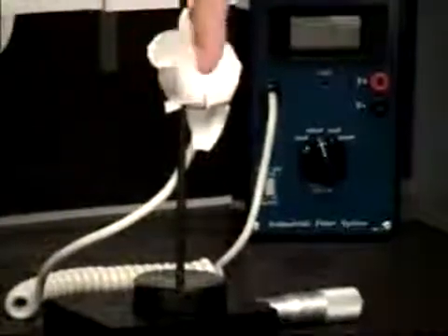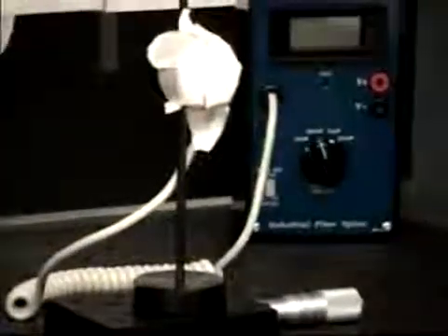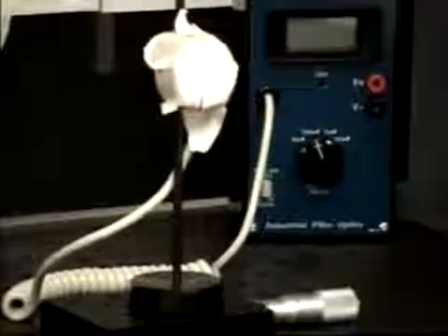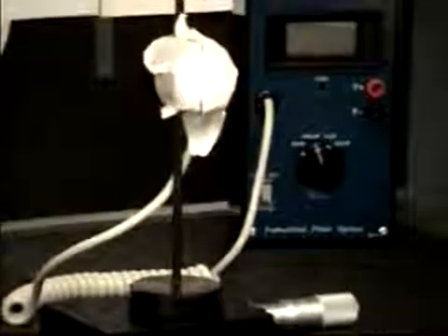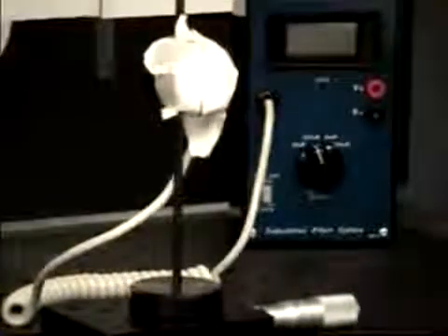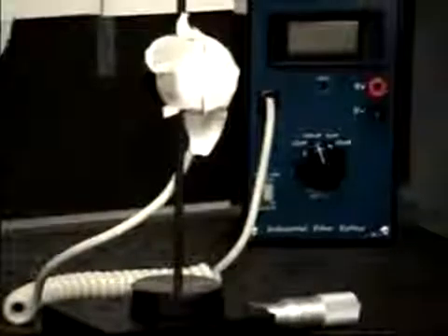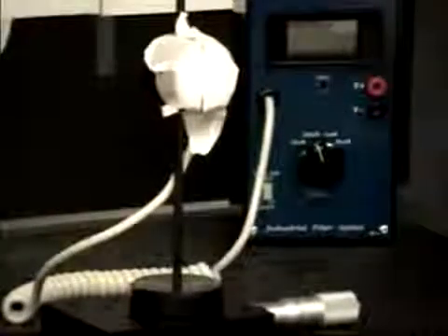That will allow us to sample the laser beam as we move the detector across. So what we are going to do is scan the detector across the aperture of the laser beam, and at even intervals we are going to measure the output power of the laser. The write-up will then take that information and graph it and compare it to a theoretical Gaussian curve for that particular laser.